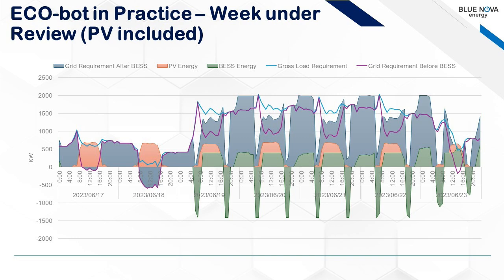Another consideration we've done is to look at this load when there is PV installed. So we have here 7 days of the week. We have the Saturday and the Sunday. And what we see here on the blue graph is the gross load requirement of the system, which has a peak of 2 megawatts, as you can see here. Now, after the BESS was installed, the grid requirement is the blocks here in gray. And what you can see, which is interesting, is that we cap the peak load at 2 megawatts so that it doesn't exceed the peak load peaks prior to the battery system's involvement.